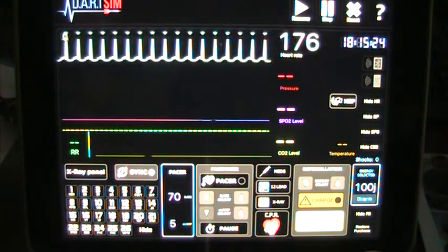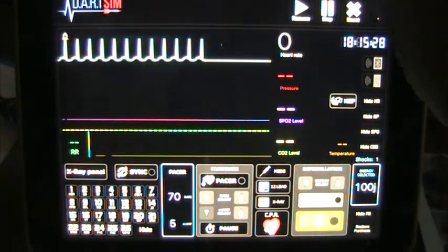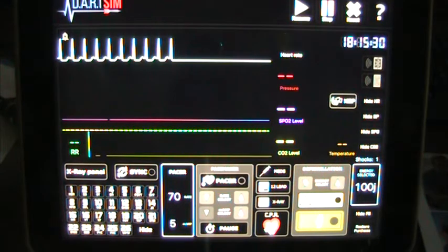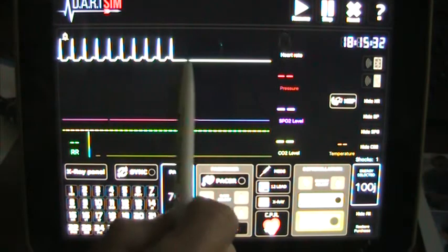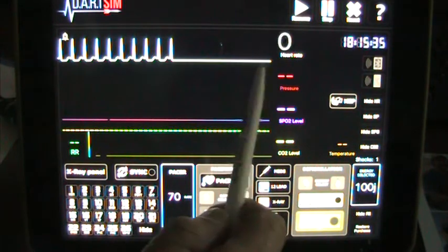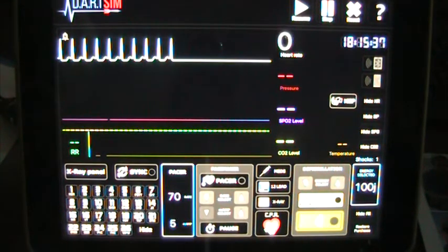I charge. I clear everybody just like I do for a defibrillation, and then I deliver the shock. Now, once that shock is delivered, you'll notice that we sent the patient into asystole. That's not a mistake. That was the intention of the therapy.